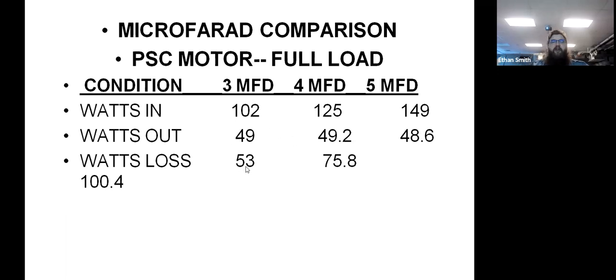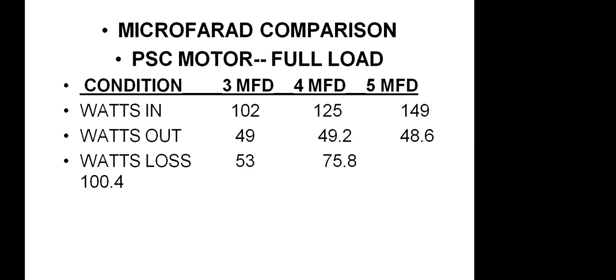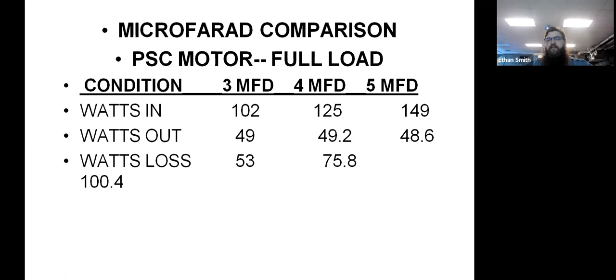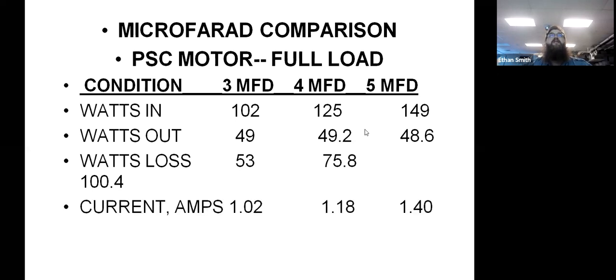Okay, where do you suppose that wattage is going? What's it turning into, guys? Must be heat. It's all heat. We don't produce light with motors unless something's gone horribly wrong. And so, yeah, you're absolutely right. That is all waste heat. So 53 watts of heat versus 100 watts of heat on either end of the spectrum, that's a big difference. Okay. And so that translates directly to motor efficiency. Okay, we can actually calculate the motor efficiency this way. We can also look at current. We see the current draw go up steadily as we increase our microfarads.